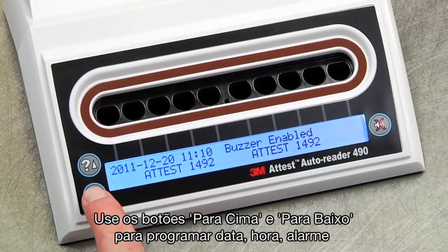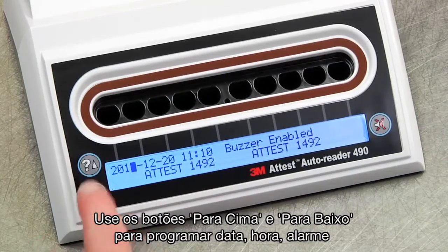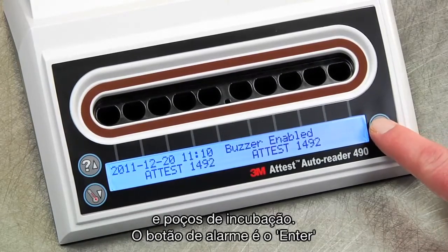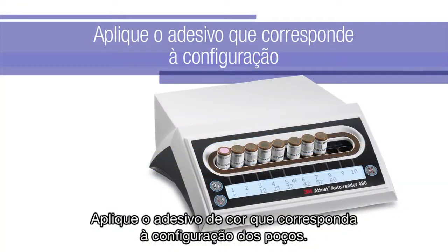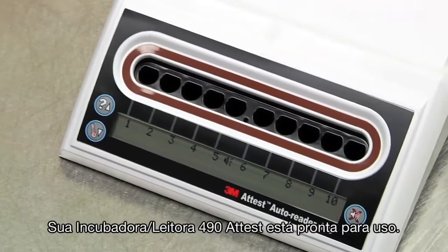Use the Up and Down buttons to program the clock, buzzer, and incubation well configuration you want. The Alarm Off button acts as an Enter key and moves the flashing cursor to the next changeable setting. Be sure to apply the color-coded sticker that matches the Auto Reader configuration that you need. Your Attest Auto-reader 490 is now ready to use.